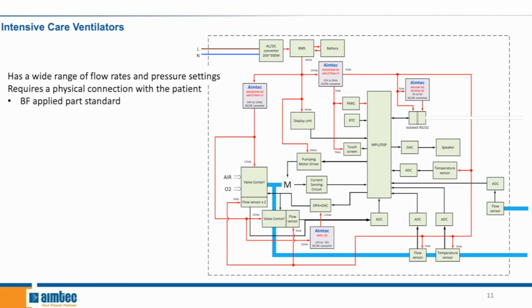In this example, the 24 volts provided by the Aimtec AC-DC converters power the display unit and the pump motor directly. 4 isolated DC-DC converters convert the 24 into 12, 5, and negative 12 volts. As the valves usually generate more electromagnetic noise, customers can use our AM10TWM-YZ or AM20EWM-NZ, all depending on the power that's required, dedicated to these valves to isolate the interference. The 5 volt levels, which is also provided by our AM10TWM-YZ or AM20 series, powers the electrical control circuits and the communication module.